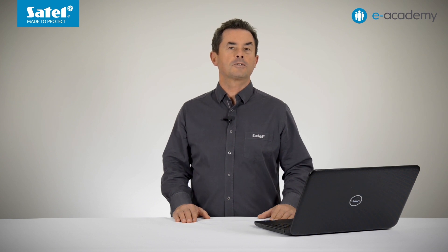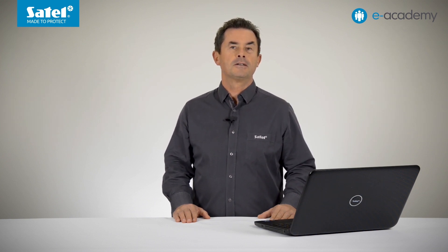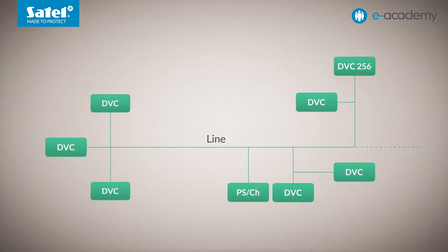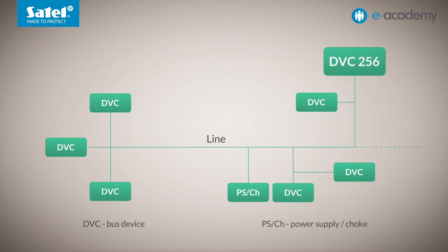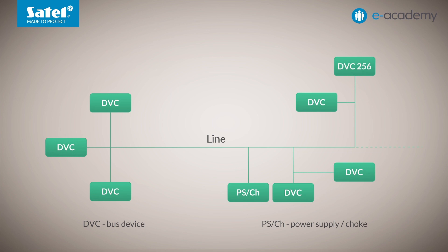I will now turn to a brief description of the KNX-TP system topology. The basic unit of a KNX installation is the line. Up to 256 devices — i.e., sensors and actuators — and a minimum of one power supply can be installed in one line. Within a single line, for example, a tree topology can be built, with branches at arbitrary points, which saves on cabling compared to a star system. It should be added that a ring structure is not used in KNX installations. The information on the maximum number of devices in a line applies to installations set up after 2018. Prior to this year, no more than 64 devices could operate in one line segment, and this number could be increased by means of special line repeaters.